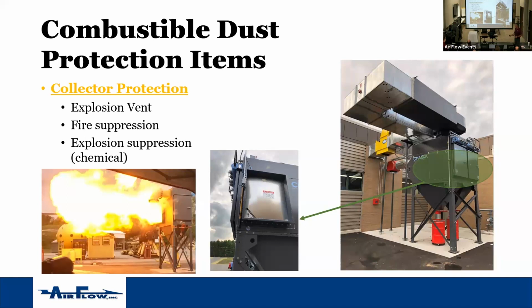There's also a device that you can get that'll mount on here. There's two different devices. One device would be just an angled baffle, and it's rated to hold the pressure of the blast, but it'll just sit on the outside of that, and it'll take that flame ball and direct it up and away. So if you're looking at protecting a walkway, or an egress path, it'll direct it up and out of the way of the people leaving. There's also an actual plenum that you can get that's constructed the same way as the collector is from the collector manufacturer. The plenum will sit on here, and this actual device will sit up in the horizontal, and it'll direct it straight up and away. More expensive than just a deflector plate, but a lot more effective at directing and controlling where that blast goes.